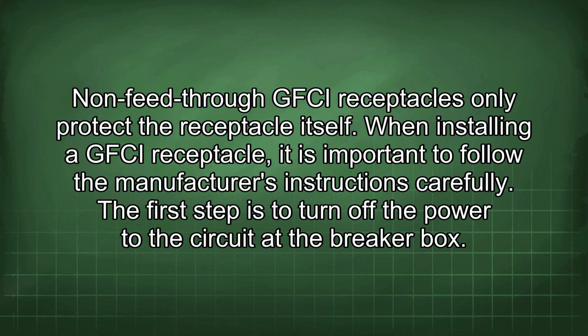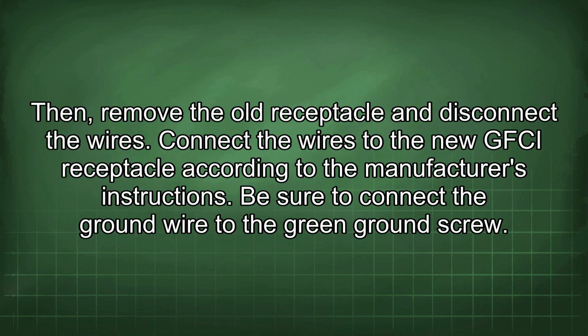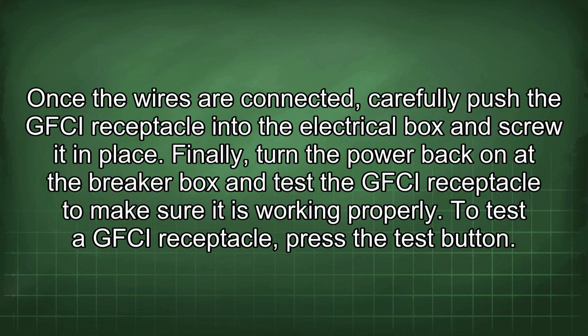The first step is to turn off the power to the circuit at the breaker box. Then, remove the old receptacle and disconnect the wires. Connect the wires to the new GFCI receptacle according to the manufacturer's instructions. Be sure to connect the ground wire to the green ground screw. Once the wires are connected, carefully push the GFCI receptacle into the electrical box and screw it in place.